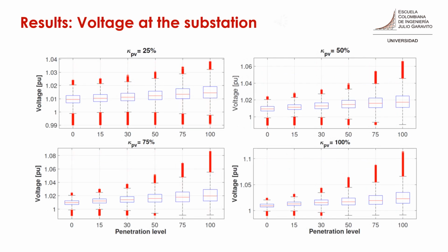It is noted that for a PV participation index equal to 25%, the voltage at the substation remains almost constant regardless of the penetration level. However, the variability of the voltage increases with the participation index. Note that for PV participation lower than or equal to 75%, there is no overvoltage in the network. The maximum voltage does not reach 1.1 per unit. In the case of 100% participation, there is a 5% probability of overvoltage occurring if the penetration is 100% as well.